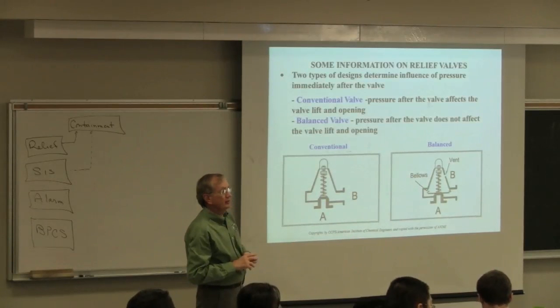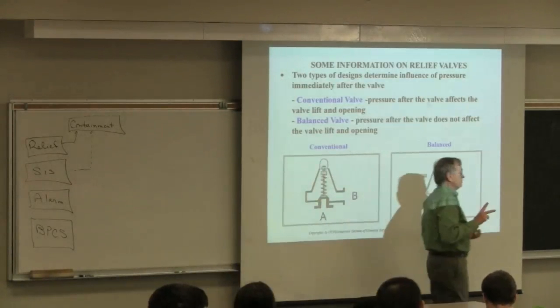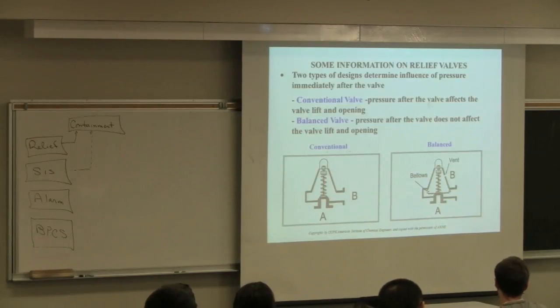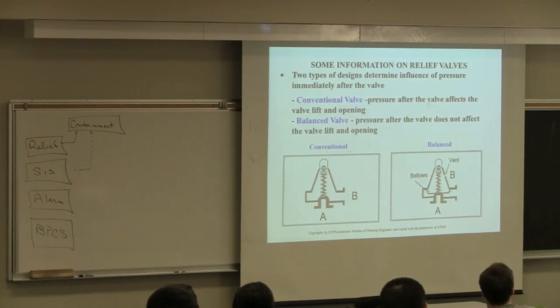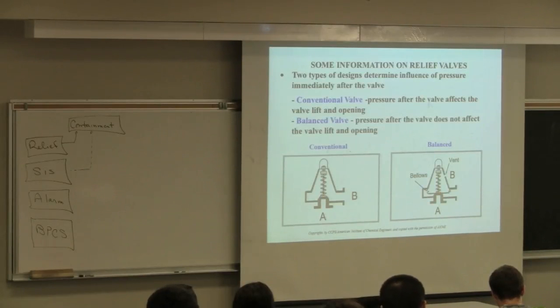On a pressure vessel, how many relief valves do you want? It depends. For example, the boilers at McMaster have several relief valves. Instead of one big valve that makes a loud noise when it goes off, you can have a series of pressure relief valves at slightly different set pressures. A small pressure excursion opens the first one; a higher pressure opens the second. So quite often you'll have several at different set points to minimize the explosive noise.